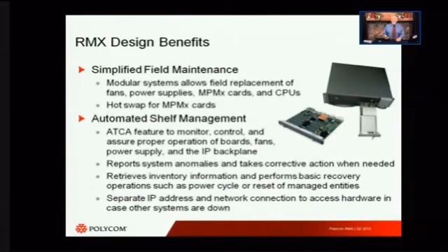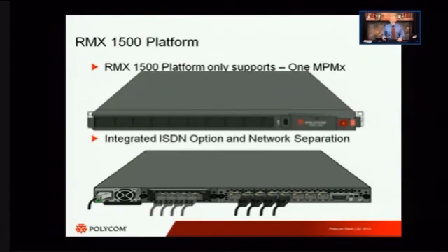And because of that, we've done some enhancements to the RMX. One of the things is making it much more field maintainable, being able to pull everything out the front. We also added something called a shelf management package. That shelf management package gives us the ability to go in, even if the control module is bad, dead, or gone, and actually do background testing on all the different other cards that are in there to make sure they're okay. That way we can hopefully fix the bridge the first time when we need to order parts when it's necessary.